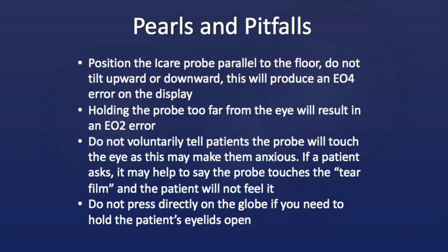Some important points to remember include making sure the Icare probe is positioned parallel to the floor and not tilted upward or downward while taking a measurement. If this is the case, the error EO4 will display on the back of the device. Similarly, holding the probe too far from the eye will result in an EO2 error displayed on the device. If you encounter either of these errors, check the positioning of the device and repeat the measurement.